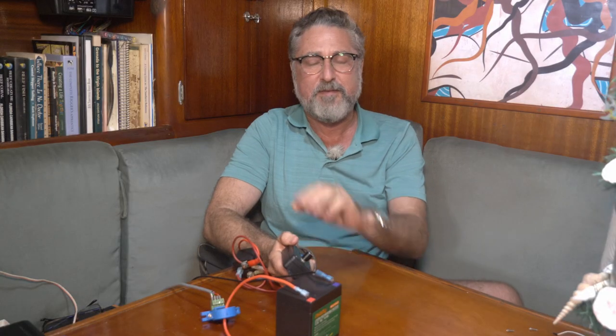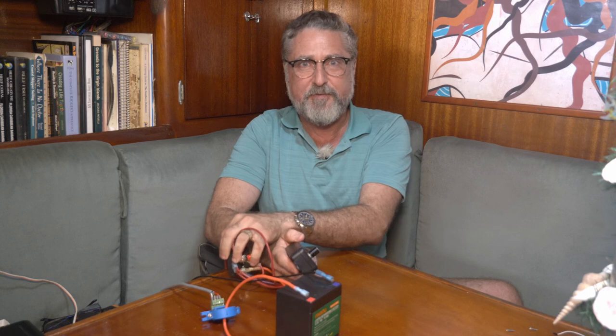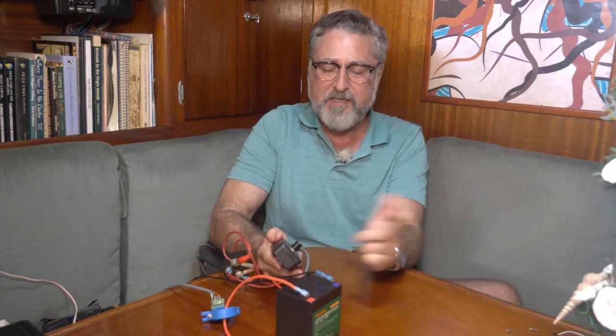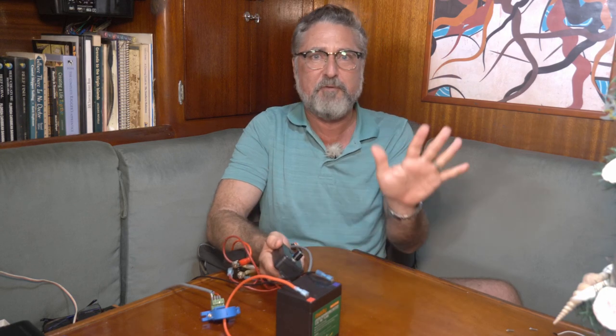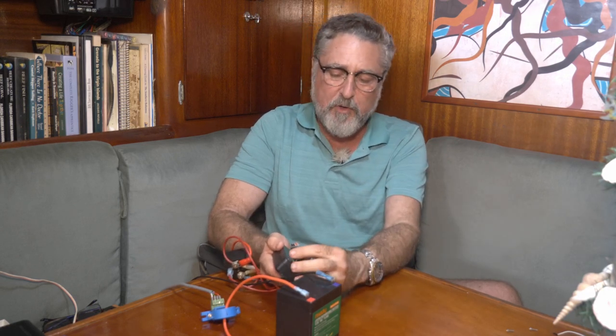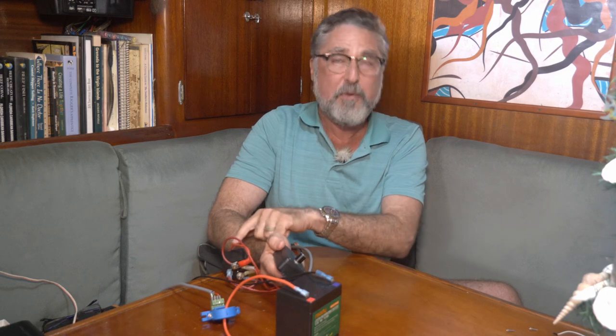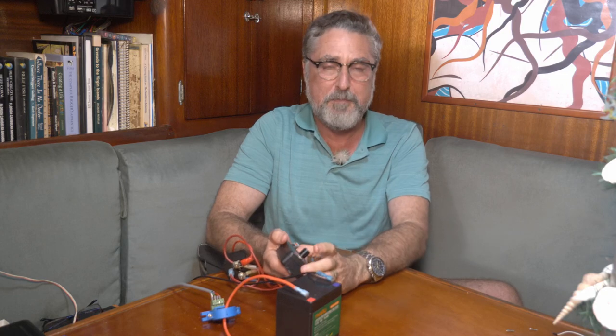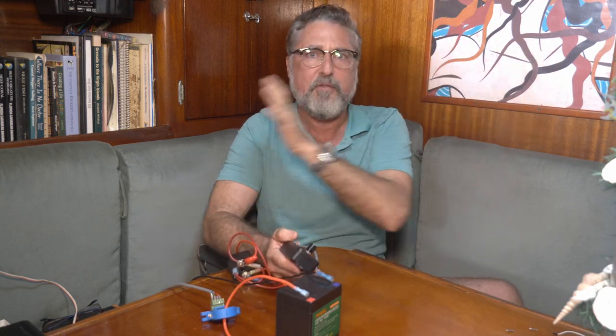When you're in the menu system, the contactor disconnects. This gives you a way of saying, just disconnect my system, just by pushing that button. And as long as you're in the menu, everything is disconnected. When you go back, it may reconnect immediately, or it may wait until it's safe to reconnect. The system will never reconnect when the battery voltages are wildly different.